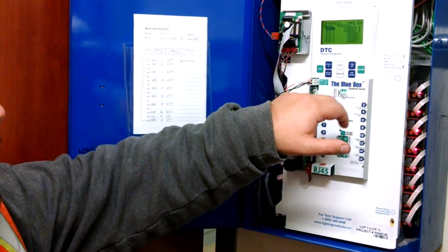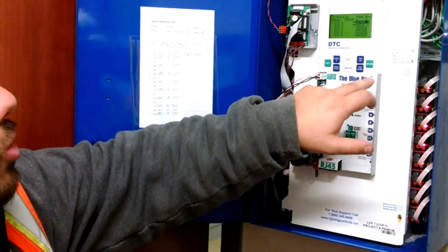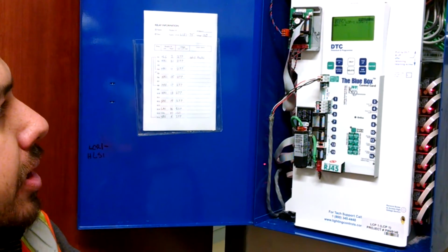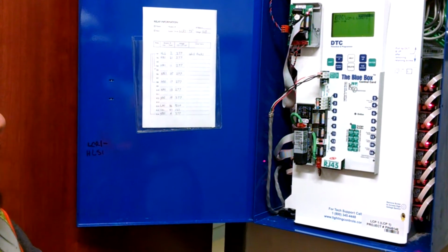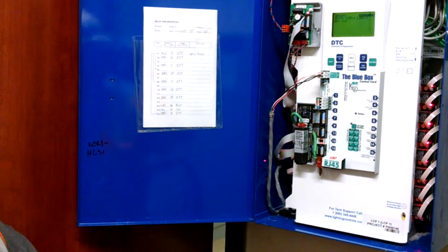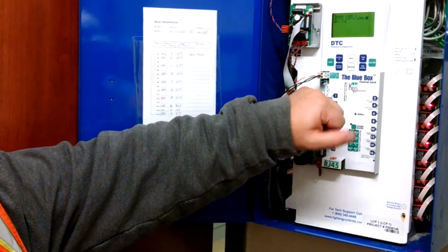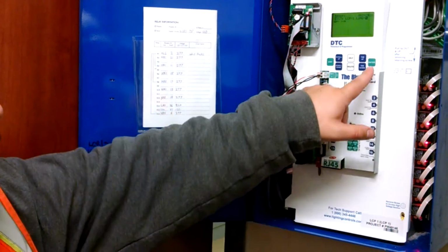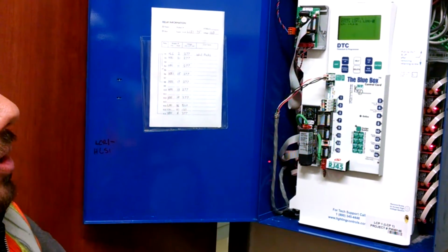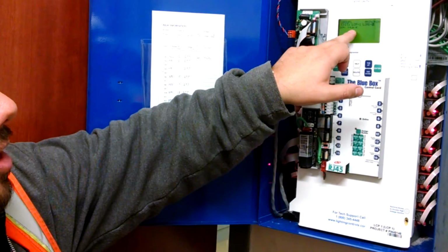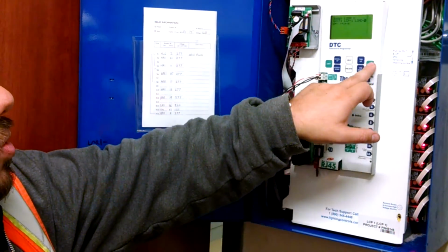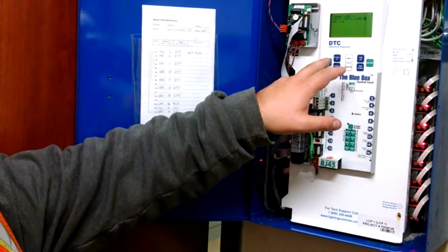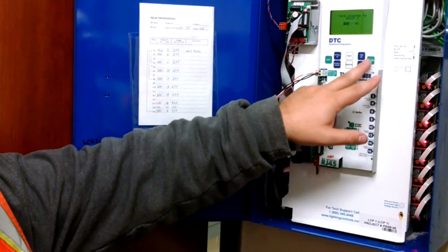Back out, back out. It's controlling group number 1, and in there you can see group number 1 contains LCP1 relays 1 through 16. Adding or removing a relay from a group is really easy. If you go to the load, you scroll up to the relay you want to add or remove, press enter. If it's in the list, it pulls it out. You can see that 5 is no longer in that list. Or it will put it in if it's not in the list already. And when you press exit, it'll ask you if you want to save.